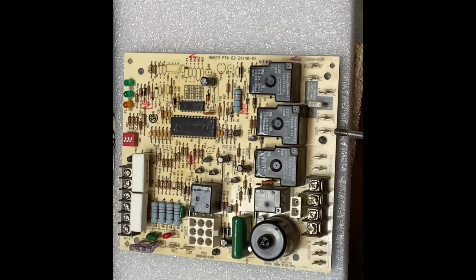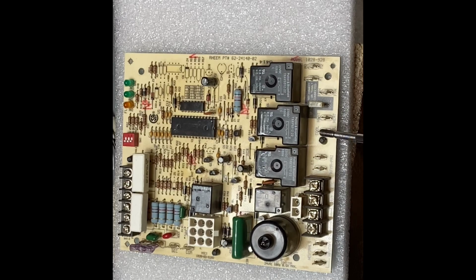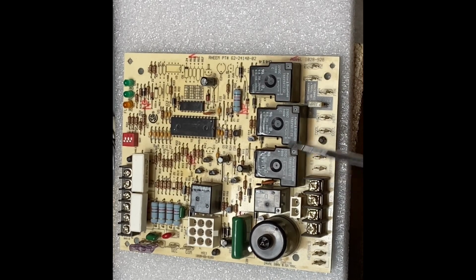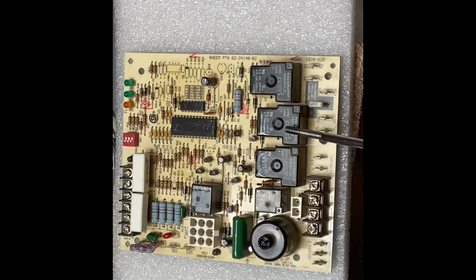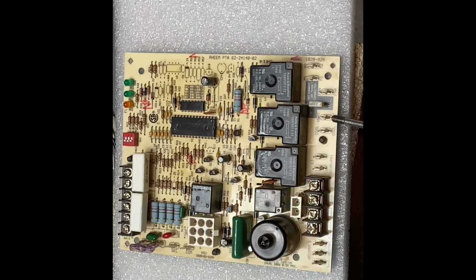Here we have where it says cool. This is the terminal that goes to our high speed for our fan motor. This relay right here actually controls this cooling terminal. We do work in the motor, we all come back to neutral. We have a separate relay controlling our heat. So this is going to be the speed used when we have the furnace running.